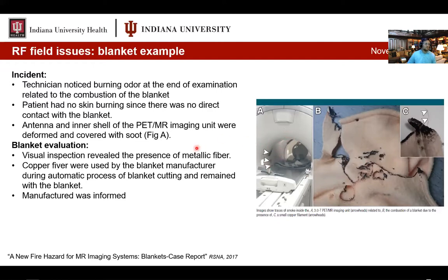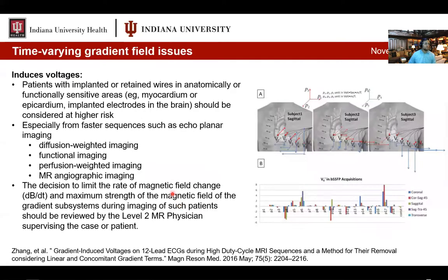And it was due to the presence of metallic fiber in the blanket. Copper fibers were used by the blanket manufacturer. So again, the blanket was not listed as having these metallic implants, these metallic threads in it. So you did not know. It is very important that we use only our approved blankets when we put them in the MR scanner.